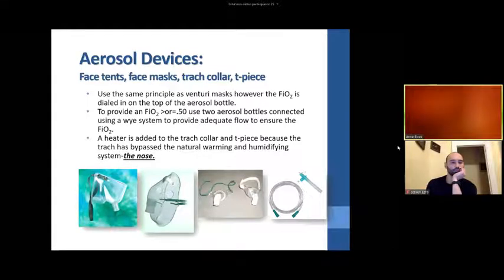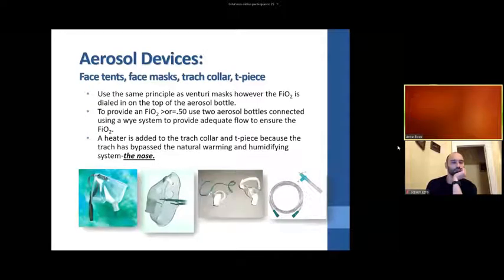Now, in terms of this, you're going to see with these masks, you can see where I've got this arrow, right? Attached to this is going to be corrugated tubing that goes to humidification. The difference here is that unlike the Venturi mask and unlike the nasal cannula, where you're going to put in a set amount of liter flow, with this type of aerosol mask that's going to have high humidity, you're going to turn the liter flow up to the highest point, to 15. And there's going to be a dial on top of the humidifier, which is going to tell you the percentage, okay? With these type of devices, I'll go over them in a second.